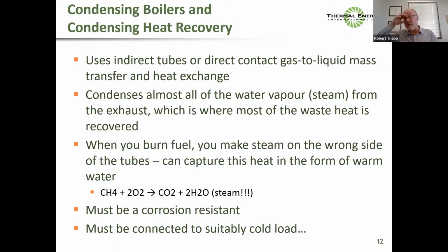But now we've got to be corrosion resistant, and we've got to be connected to a suitably cold load. So that applies to all of the condensing technologies, condensing boilers, condensing economizers. They all bring you down into that condensing space, but only if your load is suitably cold. This is a key aspect of the integration. And they must be corrosion resistant, which is why, again, the old lower heating value concept existed, being fearful of condensing in a flue gas or boiler system.